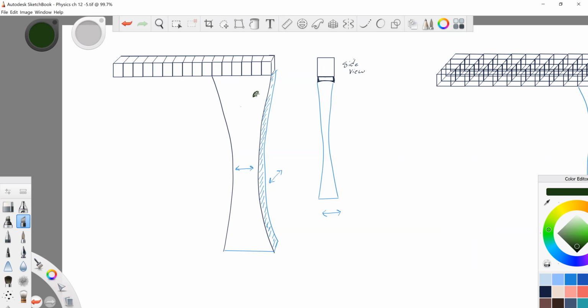If you have an object here, that's poor lateral resolution because one beam is hitting the two objects. Now it can't differentiate. However, if those two objects were further down and one was there and one was there, now one beam is seeing one object, the next beam would be seeing the next object.